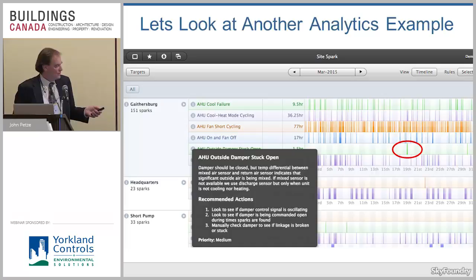Number one might be look to see if the control signal is oscillating. Maybe I have a hunting loop. Number two, maybe you look to see if it was commanded open, overridden, because maybe they were painting the space and decided they needed to flush it with fresh air 3 months ago. Number three, get a ladder. Go up on the roof, remove the dead bird, make sure the linkage is working, right? And even a priority. So engaging and providing that information to the operator about, I found this, and here are suggestions about what to do. Okay? So we've identified that.